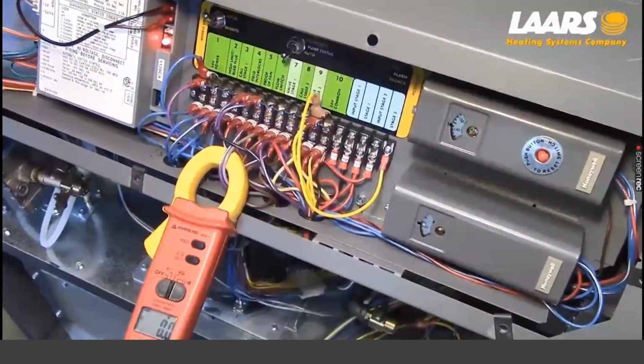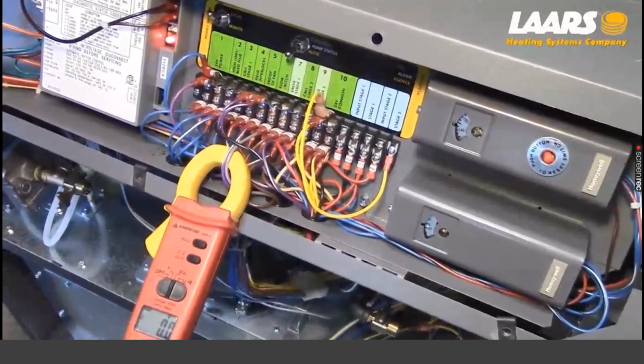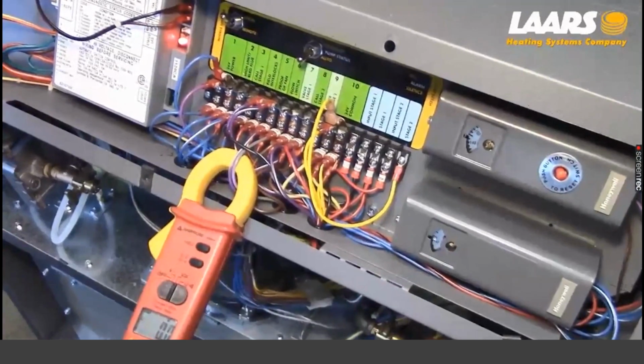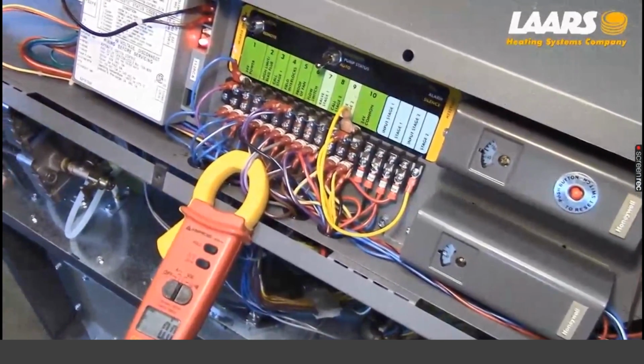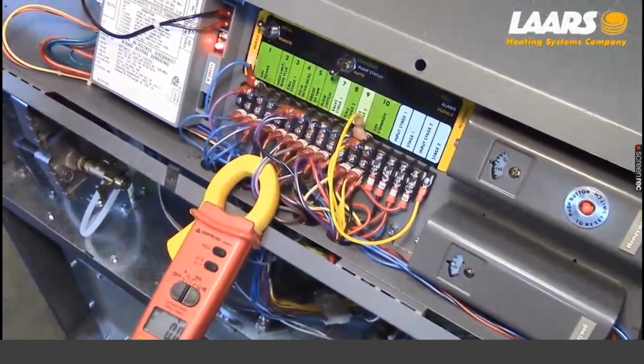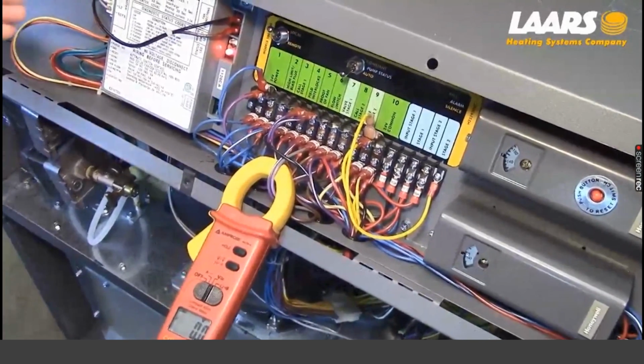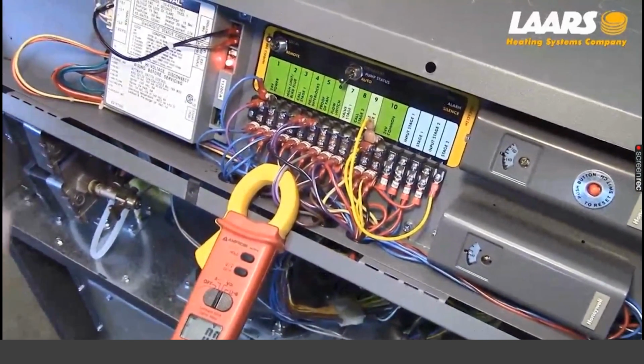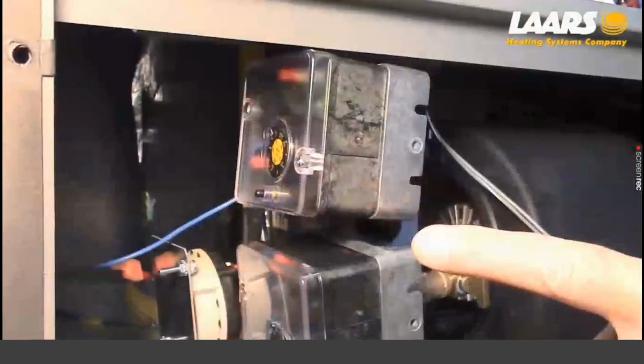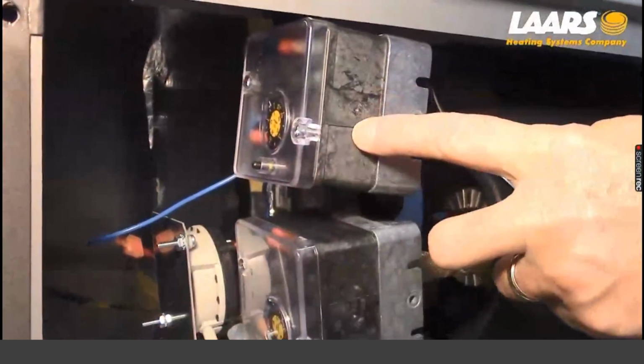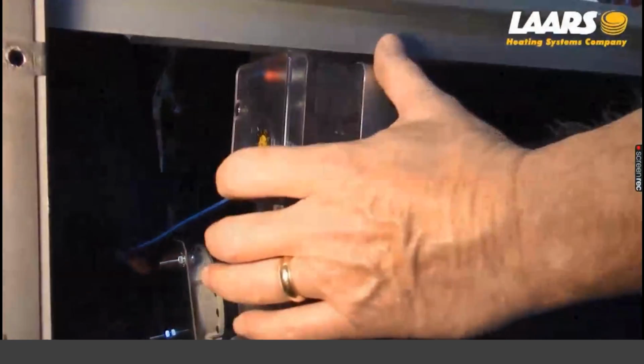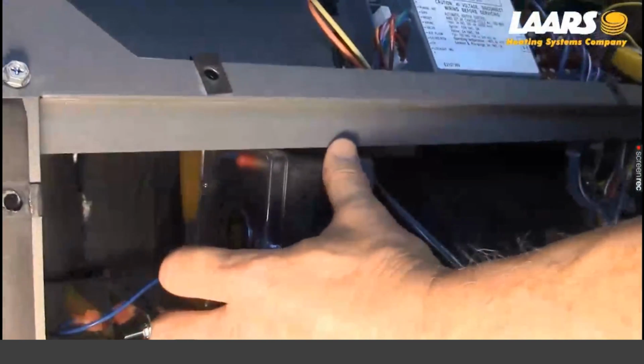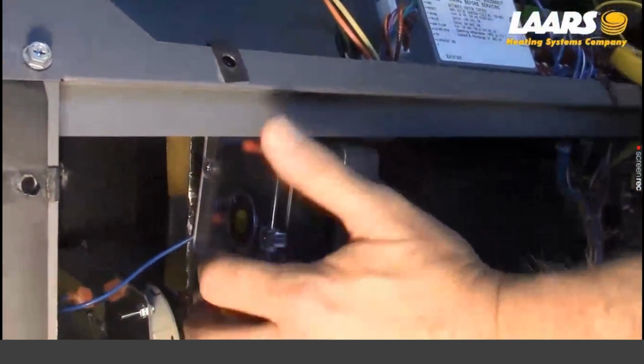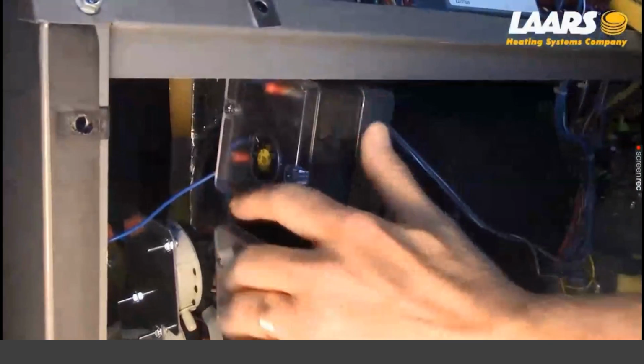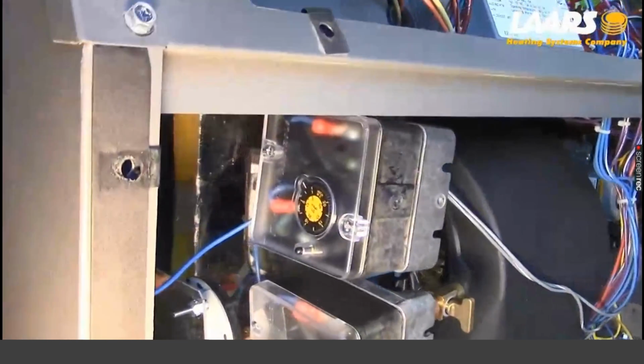safety circuit. So if you have what's called CSD1 controls, a low water cutoff, high gas pressure, low gas pressure, double check those, okay? On startup, that will be tripped on a CSD1 boiler. So in this case, I have a high gas pressure switch and a low gas pressure switch. I'm going to reset my gas pressure switches, okay, and just make sure that I have gas to the boiler.